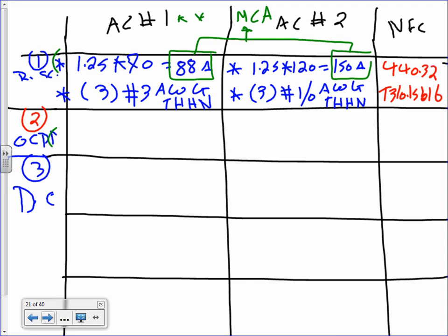If you have HVAC equipment and you look at the nameplate, or the mechanical engineer sent you the spec for the chiller, on the spec they will have a value called MCA, minimum circuit ampacity. So what is the minimum circuit ampacity? It's these two numbers. When you have the minimum circuit ampacity, Aaron, do you need to multiply this number by 1.25? No. If you have it on the nameplate, you take it immediately and size the conductor based on it.